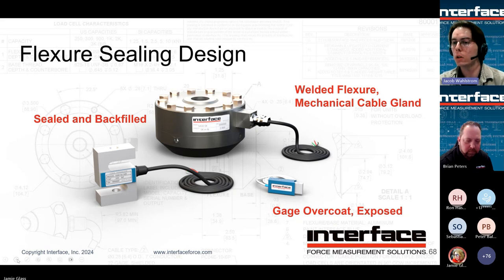So it still has a gauge overcoat, a conformal coating that we put on almost all of our load cells. But besides that, the wires and stuff like that are only protected by that cover. So if you put a screwdriver or something in there, you could ruin the load cell.